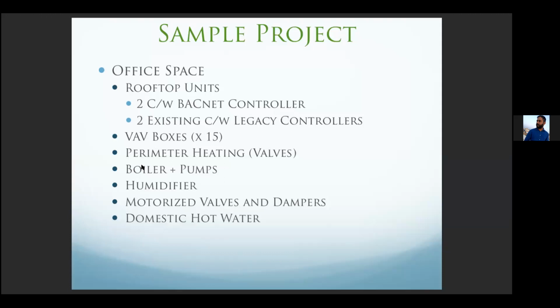Now, same thing, if these pumps have VFD, then you need to account for those VFD pumps as well. Sometimes VFDs come with BACnet as well, IP or MSTP, depending on the manufacturer, and we need to account for integrating those points at the same time. Humidifier, it's gonna be the same thing. Either it's gonna come with a BACnet card or not. If yes, then communication wiring only. If not, then we need to see what points we can pick up. At least we're gonna try to pick up start, stop, and status at least.